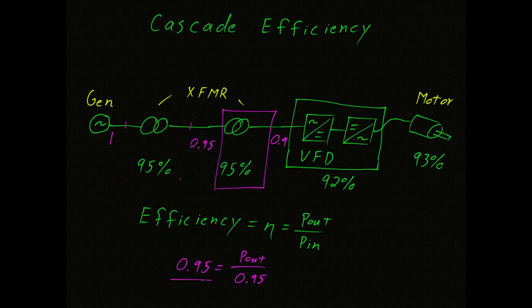Now we'll take this one step further and look at the input and output of the variable frequency drive. The variable frequency drive has an efficiency of 0.92. And the power going in is 0.9. We can see that the output power is the product of these two, which is equal to 0.83.